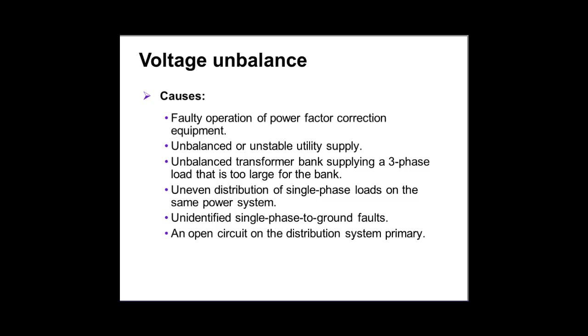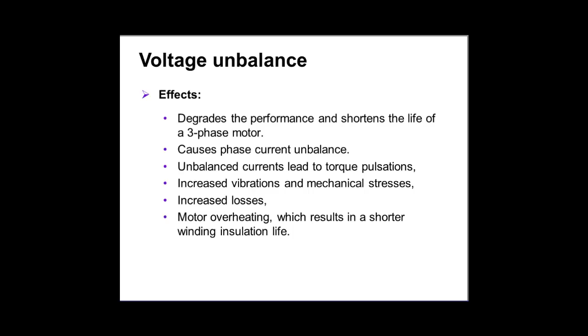Again, you can see the causes and you can see the consequences, the effects - absolutely bad, from increased vibrations and mechanical stresses to increased losses, a lot of phase current unbalances, why the insulation material being degraded, a lot of things like that.